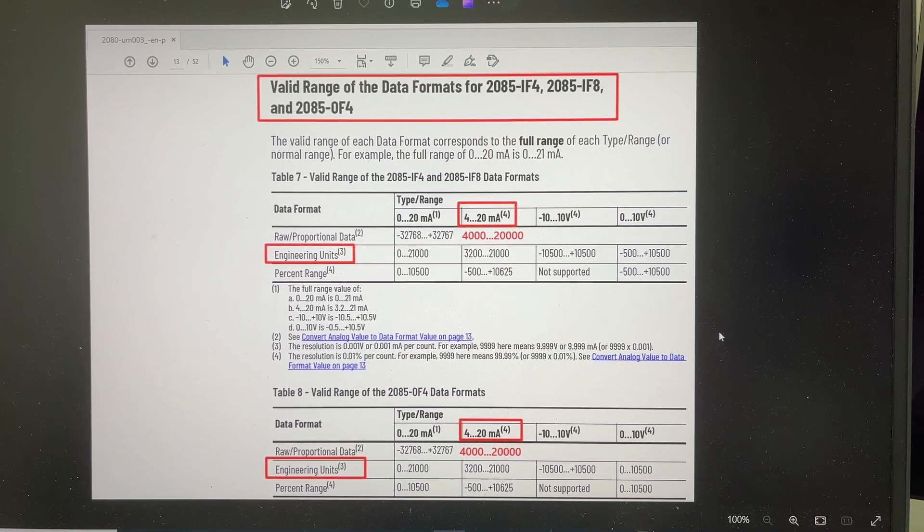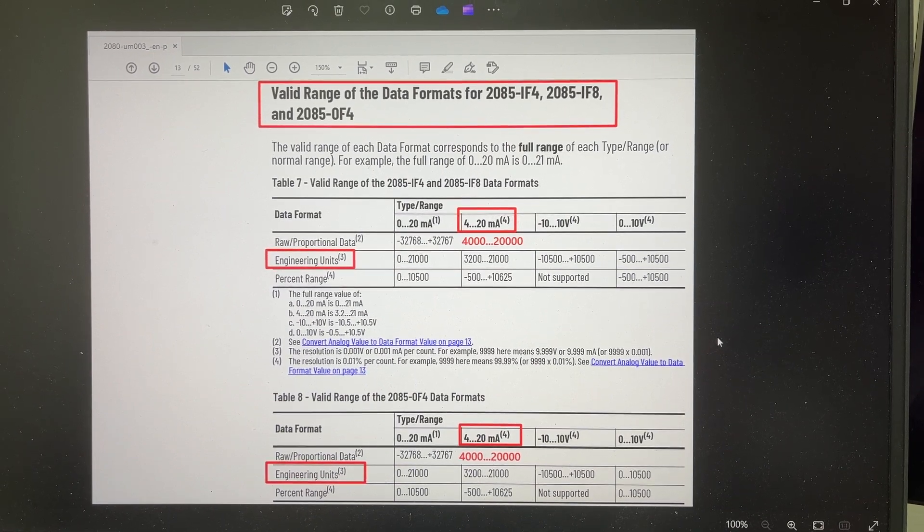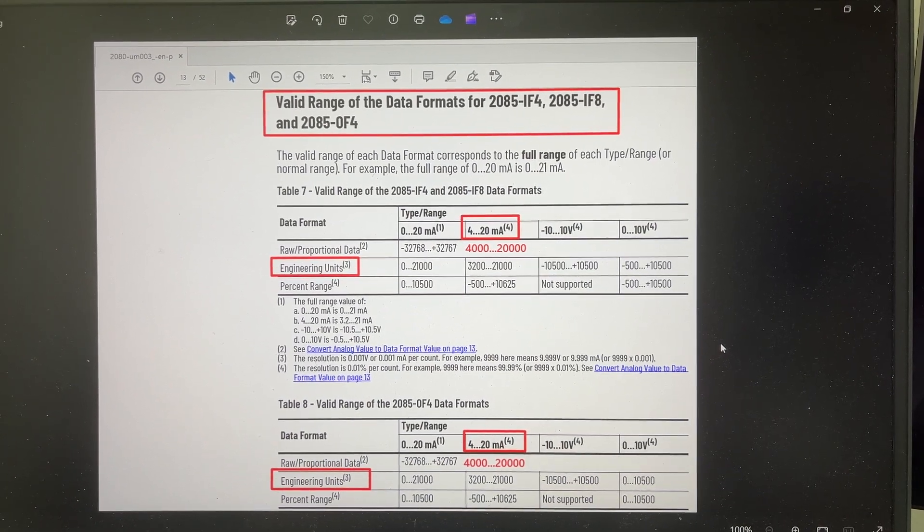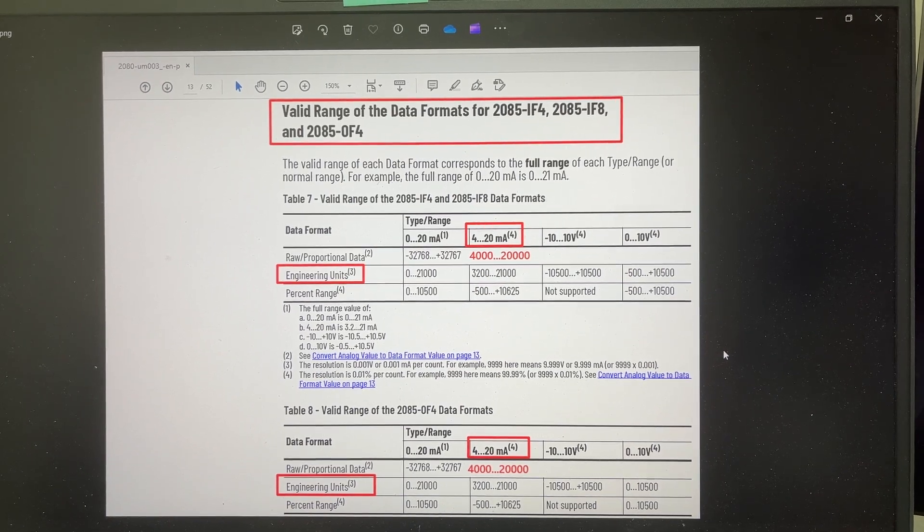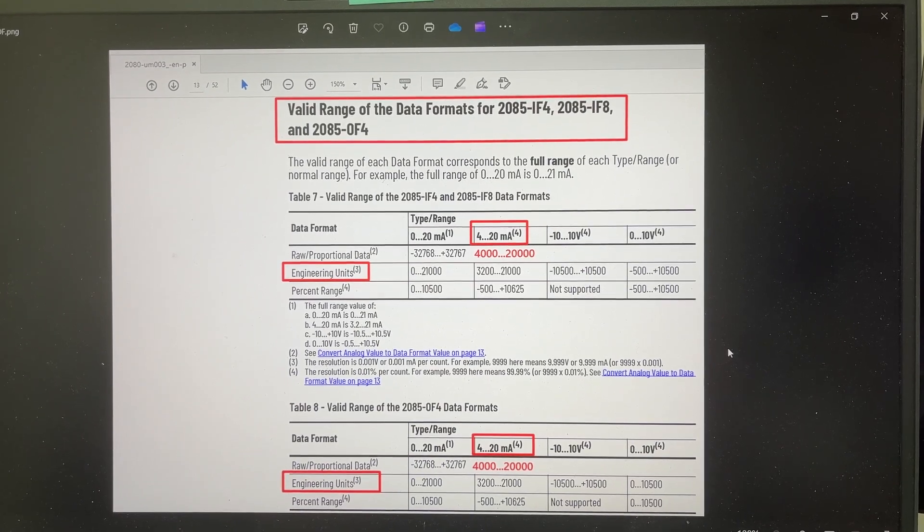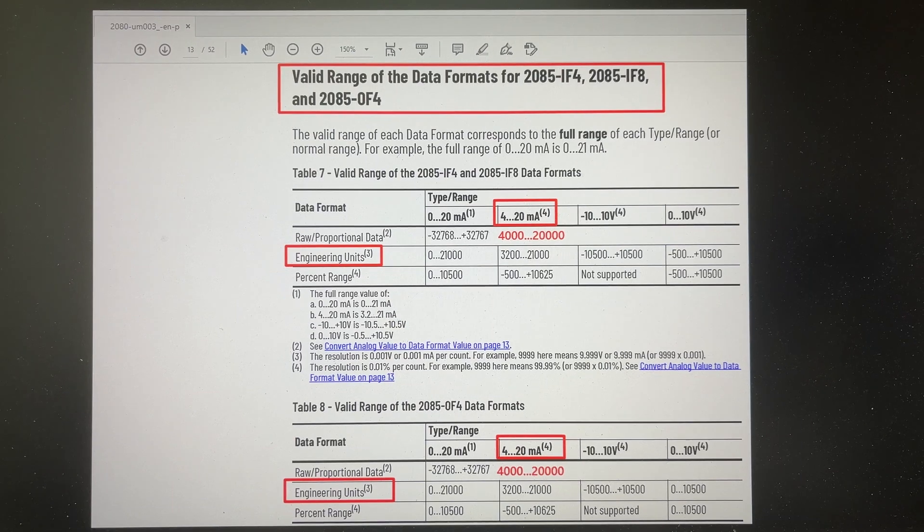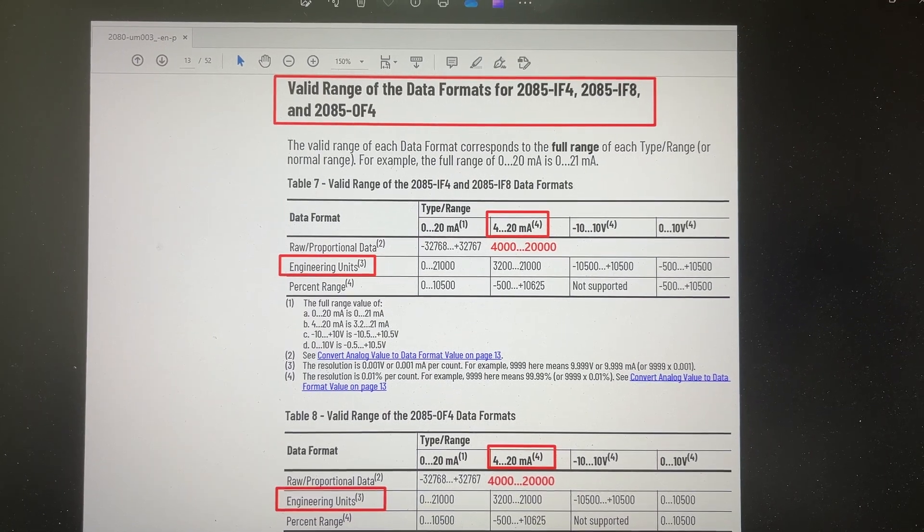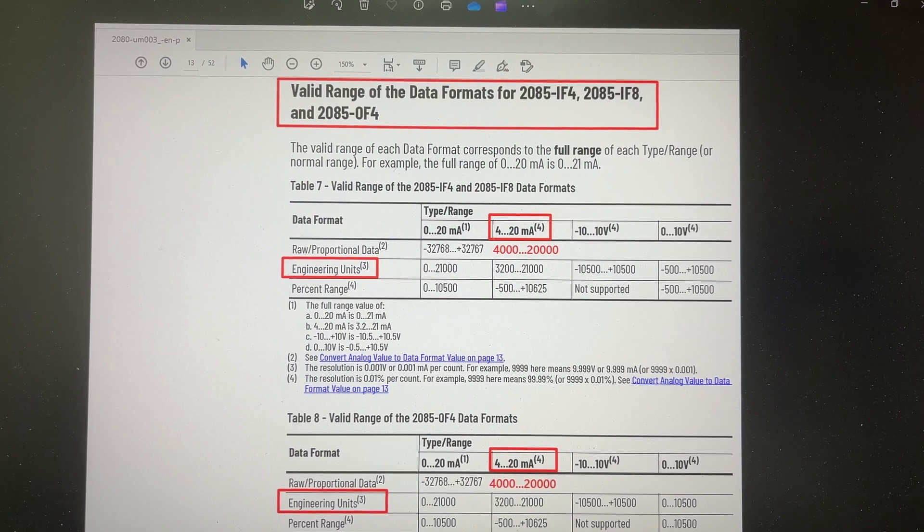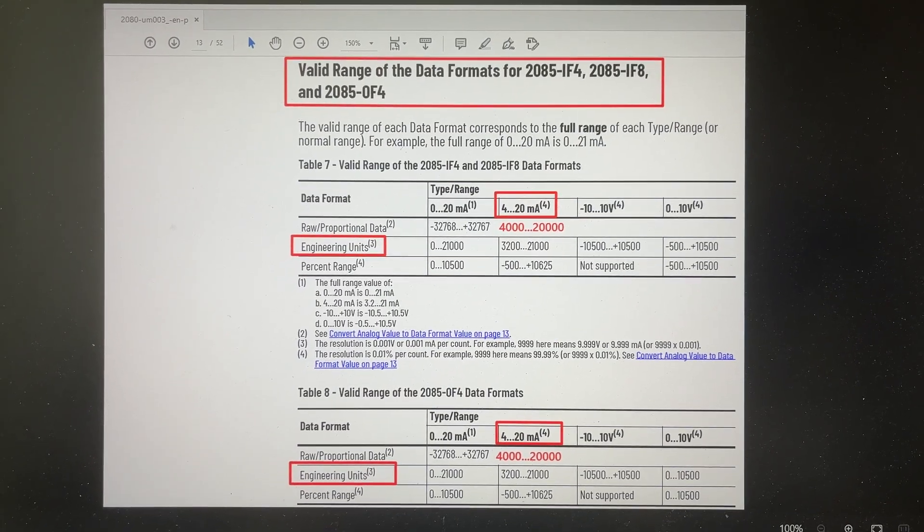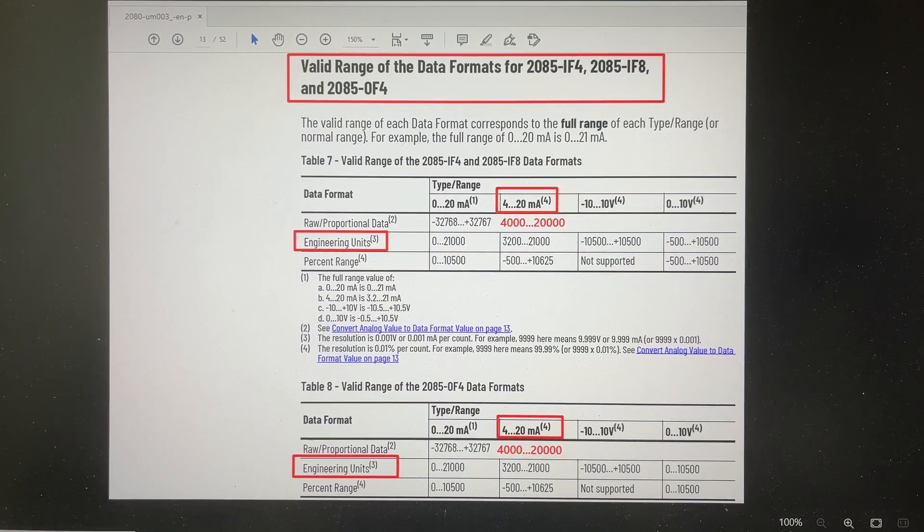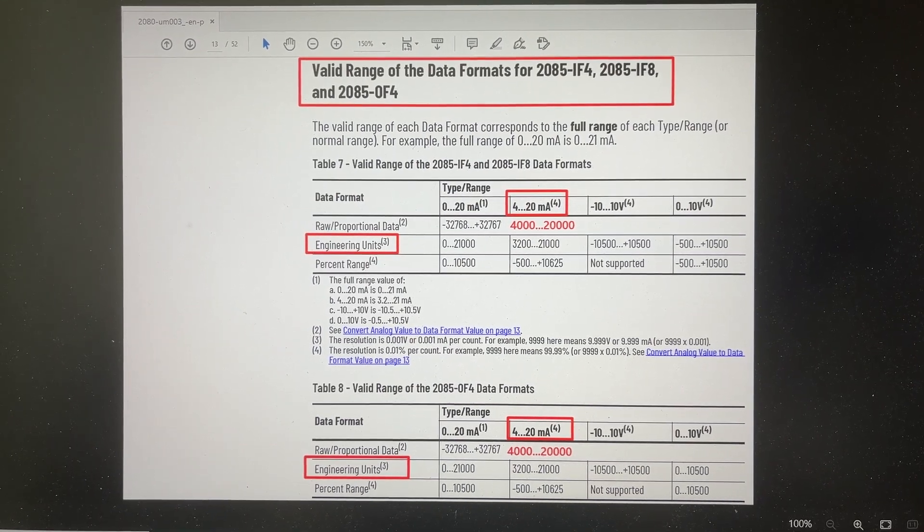This document is from Rockwell Automation User Manual. Table 7 and 8 show the different valid ranges for the PLC tags in different data formats for different types of signals from the expansion modules. Please note the full range for 4 to 20 milliamp signals with engineering unit format is between 3,200 and 21,000. However, the actual range is only from 4,000 to 20,000. The full range is a bit over and below the actual range.